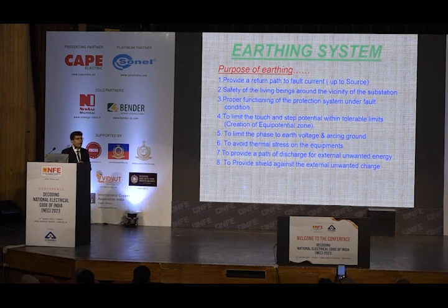Because at the time of fault, you need a dedicated path up to the source to go back. You have to talk about safety of living beings around the vicinity of your system. You have to ensure proper functioning of your protection systems under fault condition. You have to limit touch and step potential within tolerable limits. You have to limit the earth potential rise voltage, and you have to avoid the arcing ground. You have to avoid thermal stress on your equipment. You have to provide a path of discharge for external unwanted energy. Last but not the least, you have to provide shield against external unwanted charges, EMC. All these functions, whatever I have stated here, will be explained through pictures to make you understand in a simple way.